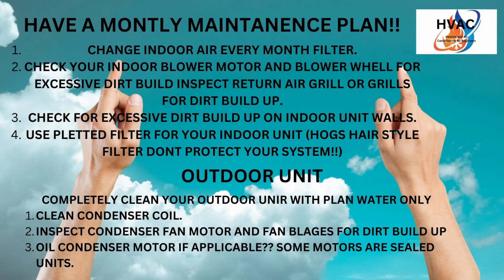That's why there's a 30-day maintenance procedure — a lot of people don't do this. They'll mow right across it or never weed-eat around their condenser, letting grass grow all around it. Did you know letting weeds grow around the condenser reduces the airflow it pulls in, since it draws air in from the side and pushes it out the top? Any reduction in airflow draws the amperage up and makes the compressor and condenser fan motor work harder unnecessarily.